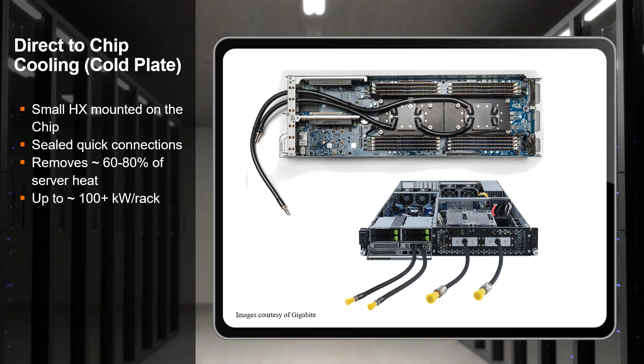Direct to chip cooling or cold plates can cool racks up to 100 kilowatts per rack and even more. If we're being honest, you can just put more cold plates in there to pull more heat out. We can change the physics of what's going on with them. Lots of things we can do to increase that capacity. That NVIDIA unit that we looked at before is being cooled by liquid cold plate. And so we know that it can do that 120 for sure.